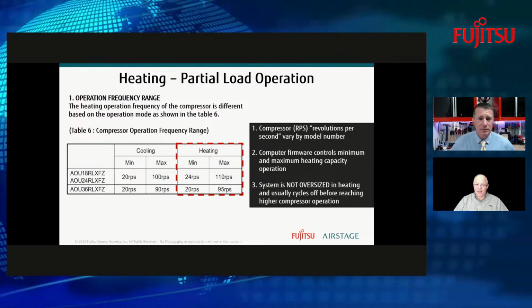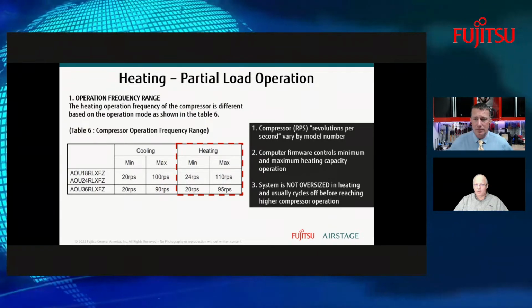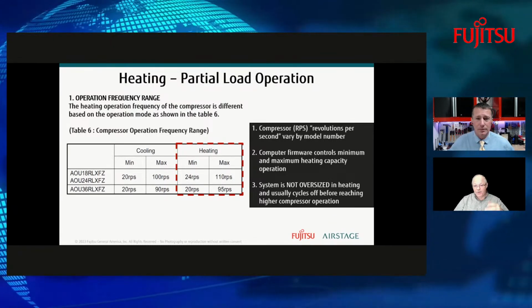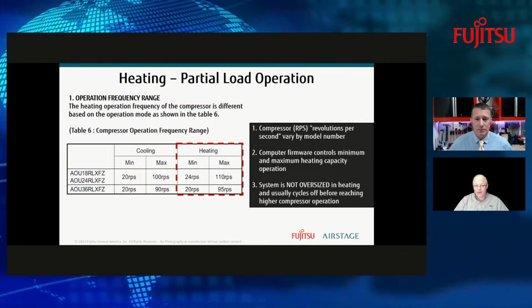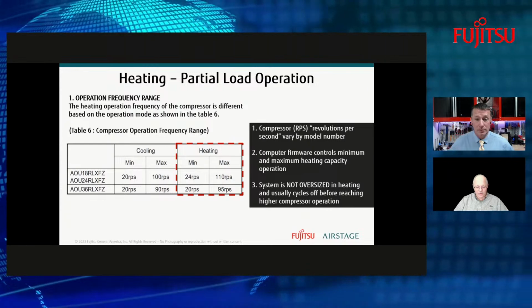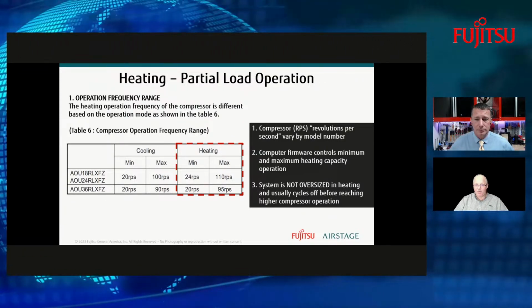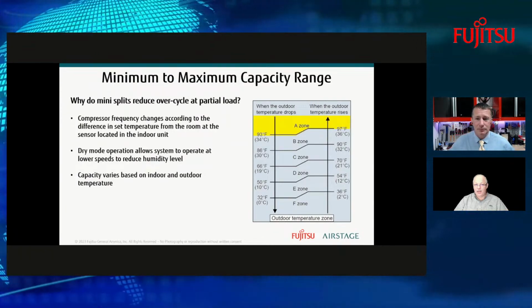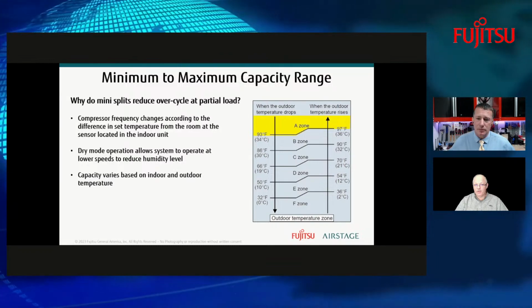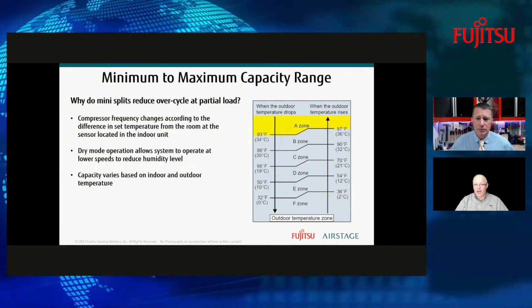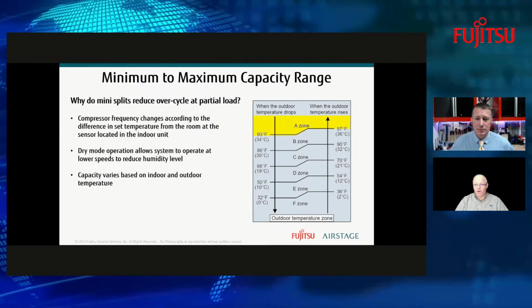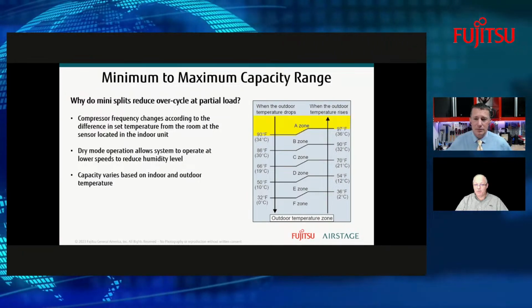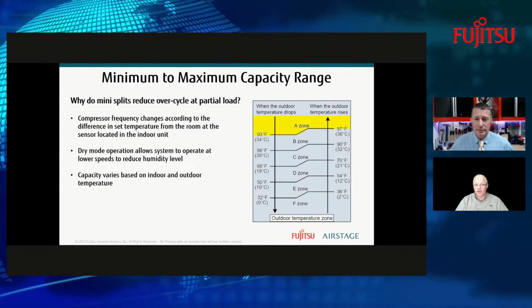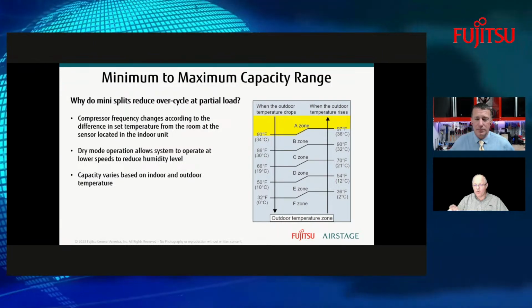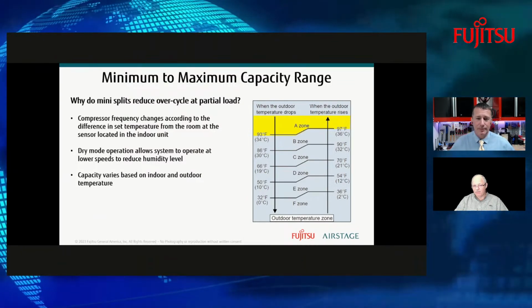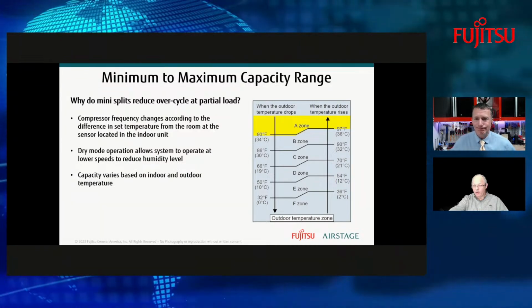So again, when we get into heating, there's partial load operation. We talked a little bit about the speed of the compressor. This one has a range of 24 to 110 on an 18 and 24, and 20 to 95 RPS on a 3-ton. So it's going to have an operating frequency range as well. We also talk about reducing overcycling. This is big for utility companies, because they ask, how do you keep from overcooling a space if you're designing this based upon a winter temperature that's really brutal? Well, that's because the system has a wider operating capability.